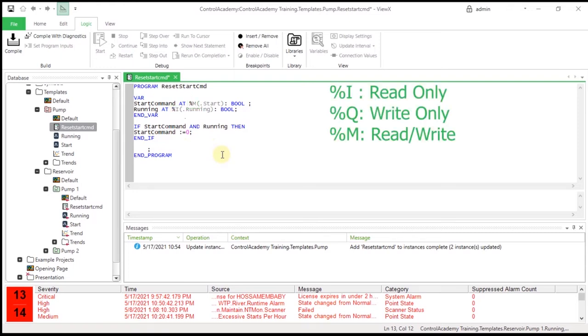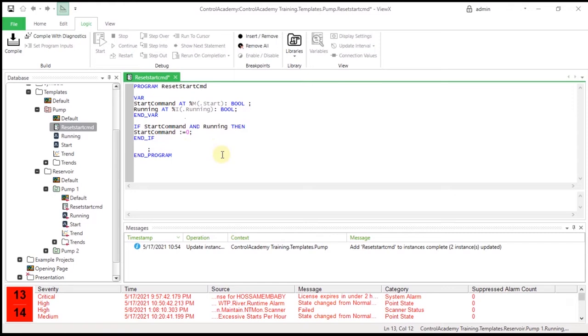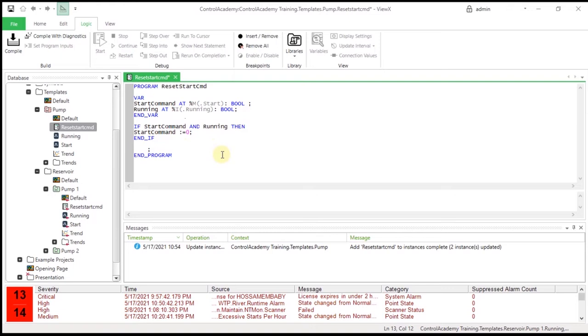The character before the database object name defines the access type. Percentage I means read only. Percentage Q means write only. And percentage M means read and write. Everything before END_PROGRAM is the body of the code. In this case, the code says that the server should turn off the start command if it is currently on and the running feedback is active. The END_PROGRAM statement marks the end of the structured text program.